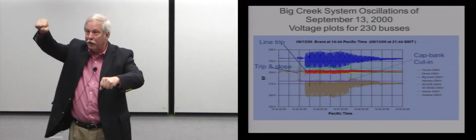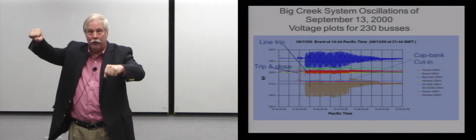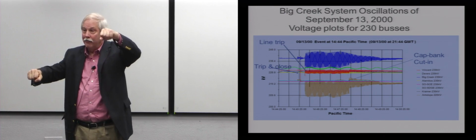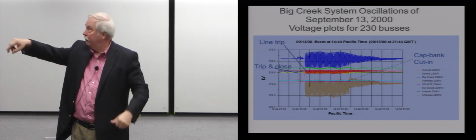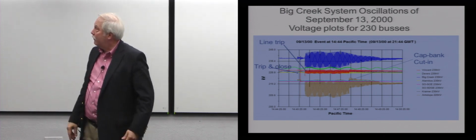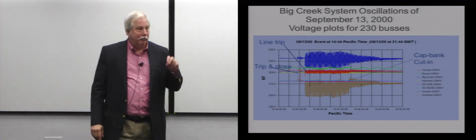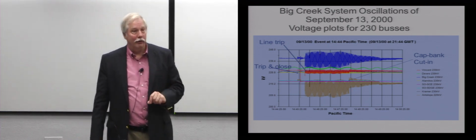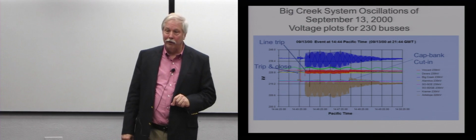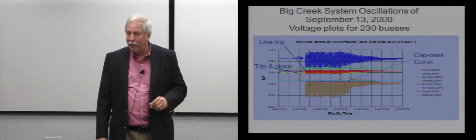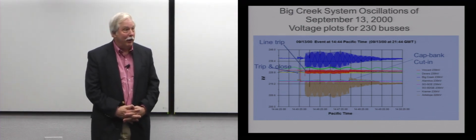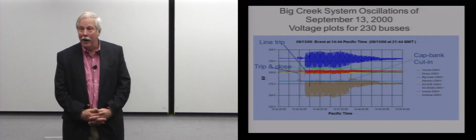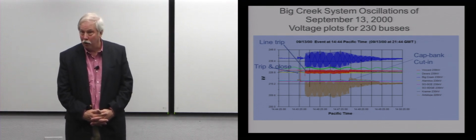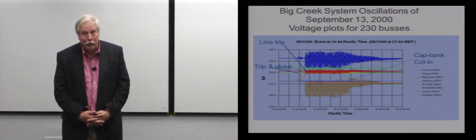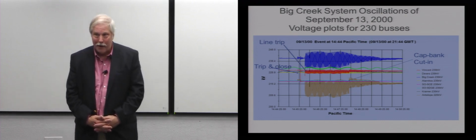In the lockout mode, the power system developed a sustained oscillation. Imagine two generators swinging back and forth against one another at very, very slow speeds. The frequency of that oscillation is 0.6 hertz - very, very slow. I was talking to Pratap earlier, and he said he's seen some of these oscillations now as high as 13 hertz.